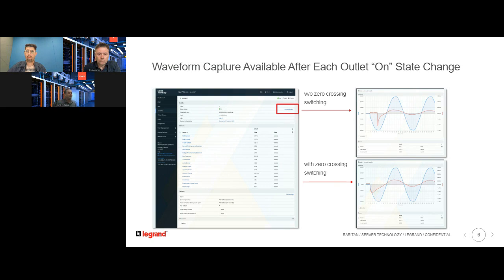And that does a couple key things, really. One, understanding a current inrush problem, and if you've got one or not, and then how you manage it by the order and how you cycle on the relays is really key. And you were talking about the high density and the high wattage on the power supplies today, and that really all ties together as part of that functionality. Also, you could use it to understand maybe you don't have a current inrush problem, and whether you'd want to use a switch PDU or maybe not want to use a switch PDU.